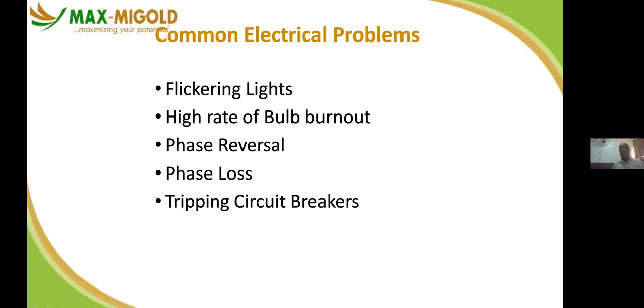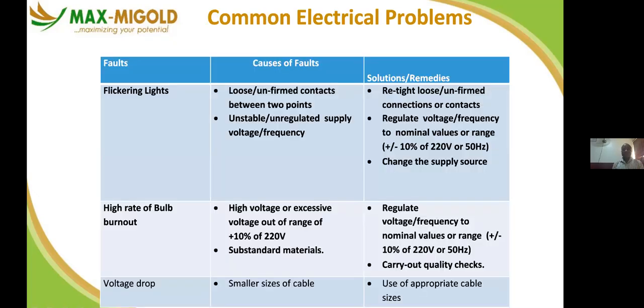So we have common electrical problems in the building. We have flickering lights, high rate of bulb burnout, phase reversal, phase loss, tripping circuit breakers, and so on. These are common things we experience in our installation, in our facility. So there are causes and there are solutions. What causes my bulb to flicker? It could be loose or un-firmed contact. That's partial contact. So what do you do? You check and retighten the loose contact or the loose connection.